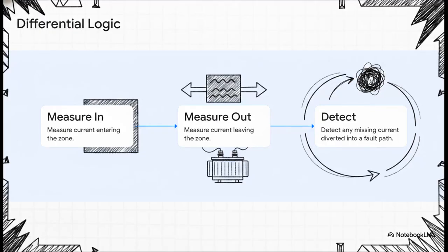So how does it actually catch this? Well, whether it's an obvious external bushing flashover or one of those sneaky, deep interturn shorts, the relay relies on a beautifully simple principle. Step 1, it measures the exact current entering the transformer. Step 2, it measures the current leaving. And step 3, it compares them. If the current entering one side suddenly doesn't match the current leaving the other side by an amount diverted into a fault path, it detects that missing current, and bam, it triggers a trip.